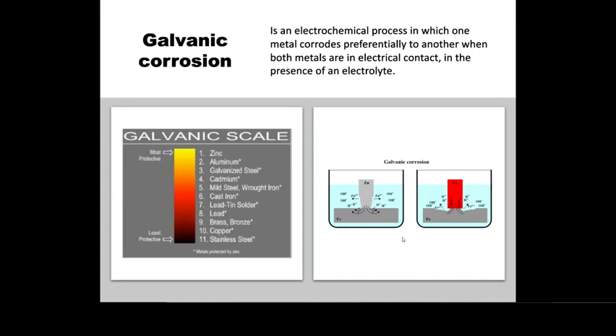So, for example, you've got an existing galvanized steel water pipework in a house, and where the brass hose tap's joined on, sometimes it will stop working or clog up, and you take the tap off, the tap seems okay, take the tap right out, and you see that there's a whole big pile of corrosion inside the steel fitting. And that's because the contact with the brass has hastened the corrosion of that pipe, and it may even block the water flow.